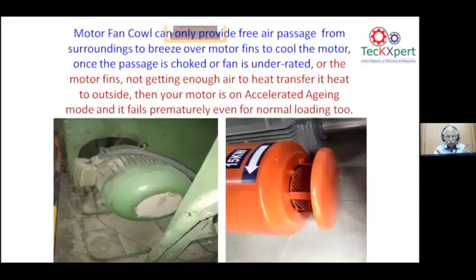You see two types of motors. The fan cowl is supposed to facilitate the air passage through the fan to the motor. Depending on the industry and the environment, the fan cowl has to be selected. This problem identification tool is one of the problems identified in many industries. Is the motor's non-drive side getting hot because there is no air passage at all? This can be corrected by the one on the right. You can see the do's and don'ts type of image on the right side.